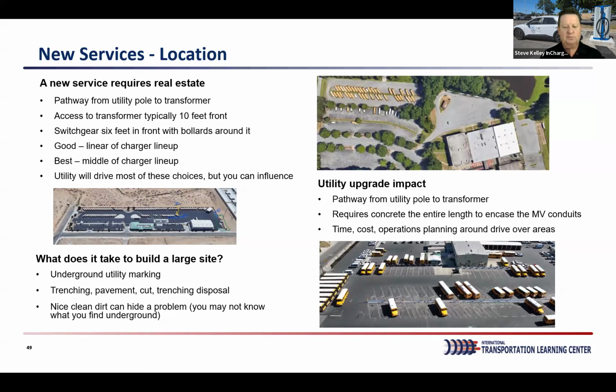In many cases we're planning not just the initial phase but phase 2 and 3 of converting to electric, to make sure we've minimized cost and made the installation really efficient, so we're not going back out to install more trenching or cut into the ground in the future. We tend to install a lot of additional conduit for future-proofing, so you save cost and don't impact the yard later. These are some of the things we look at when installing new service or doing on-site work, to make sure we're in there one time and can leverage that infrastructure in the future.